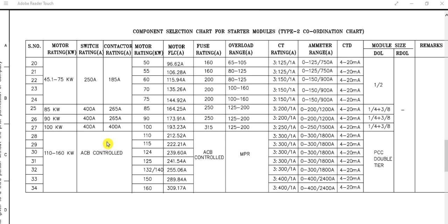So this is an air circuit breaker for higher rating motors. Generally we consider air circuit breakers for the LV low voltage incomer and bus coupler breakers. And for these motors, from 110 to 160 kilowatt, which are higher rating motors, we will not use the fuse or contactor, because this will be air circuit breaker operated. So this is ACB control. The motor full load current for this 160 kilowatt motor is coming 309 ampere, and there is no fuse because it is ACB controlled.